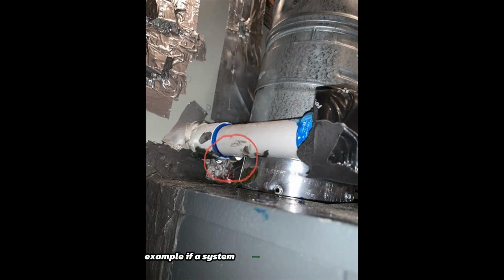Example, if a system removes water from the air and it drips from the drain line, that's latent heat removal in action. You're condensing water vapor into liquid, and that takes energy. Why is this important? Because total cooling is the sum of sensible heat plus latent heat equals total heat removal.